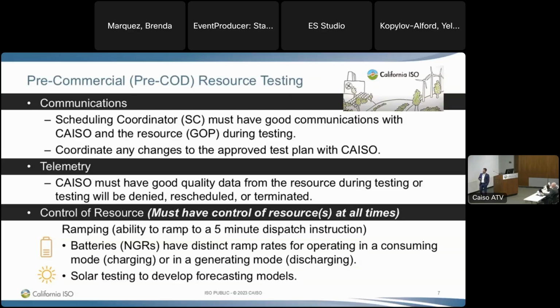So under no circumstance should you be doing instantaneous full charge to discharge. Is it cool? Yeah, it's pretty cool. It's pretty remarkable you can move that fast, but it's going to cause a system issue. And the reality of it is we've actually had some WECC-wide disturbances in which the batteries move so fast that our AGC reacts to it, and then other BAs' AGC also reacts to it because the tie flows move. So essentially the whole interconnection starts to shake together. Do you want to be the battery that does that? No, you don't. You don't want to be the battery that caused the whole system. So ensure that you have those ramp rates defined and ensure that you're doing that 5-minute ramp rate rather than an instantaneous ramp. Any questions on that?